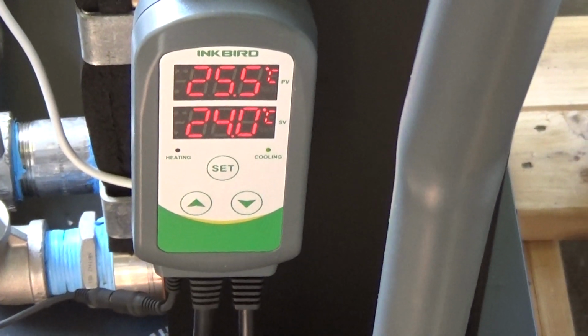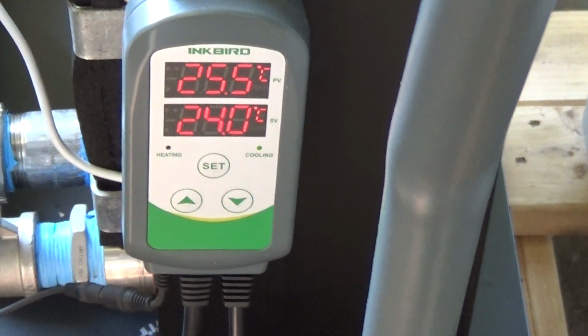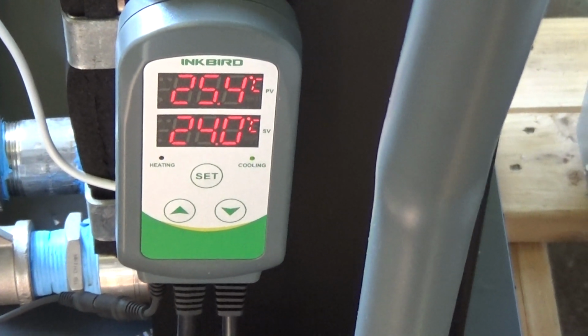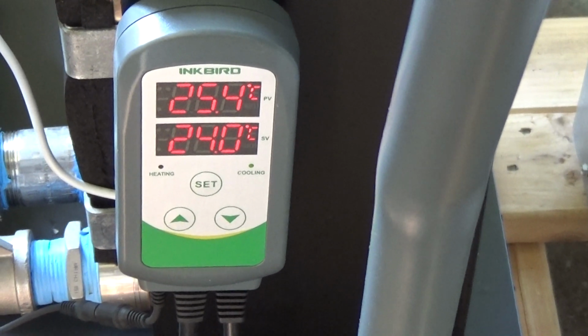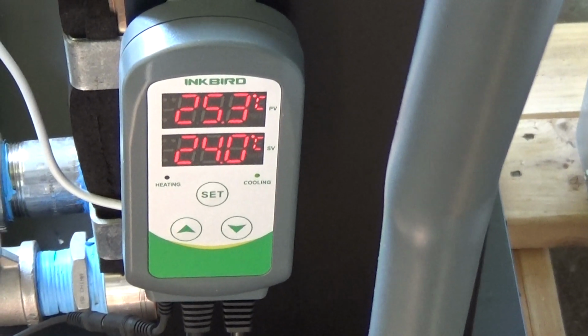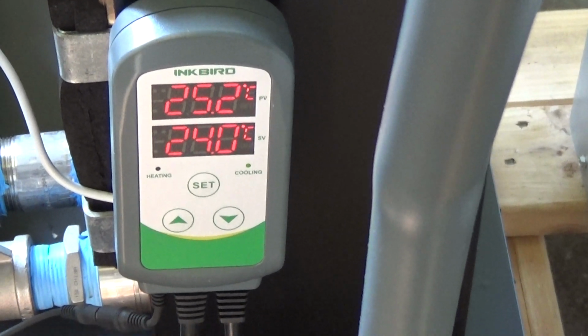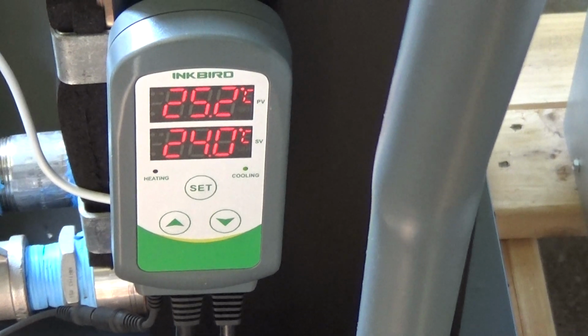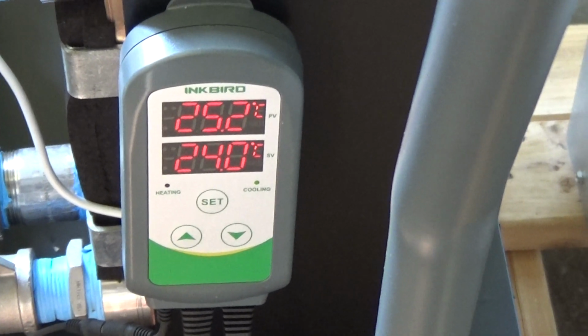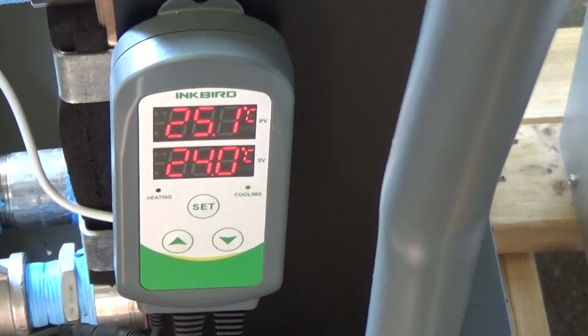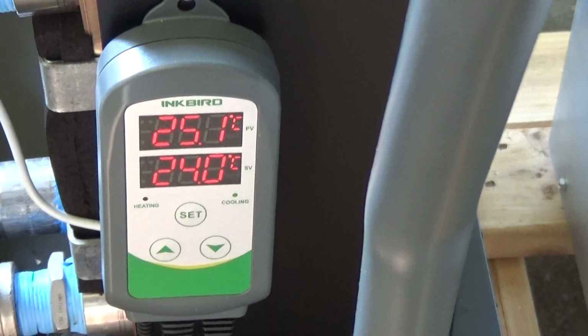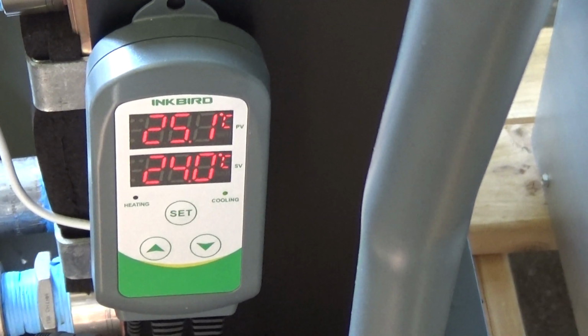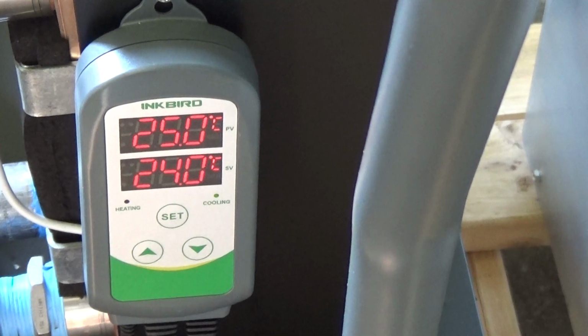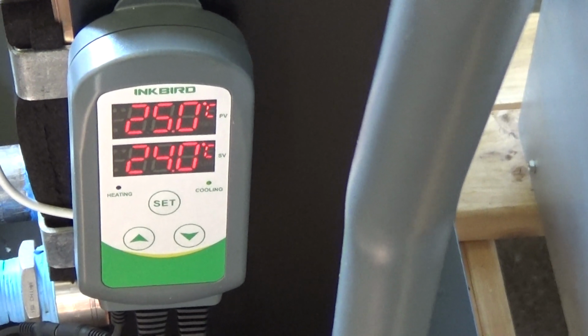As we get closer, once we reach the set point, it'll take a couple seconds. That motorized ball valve will then close, thus bypassing the chilled water flow to get our precise control. Right now, we're just cooling with the chilled fluid that's in the glycol tank of the chiller. The compressor and fan's not on, but now you can see it just turned on, and we're starting to chill again.